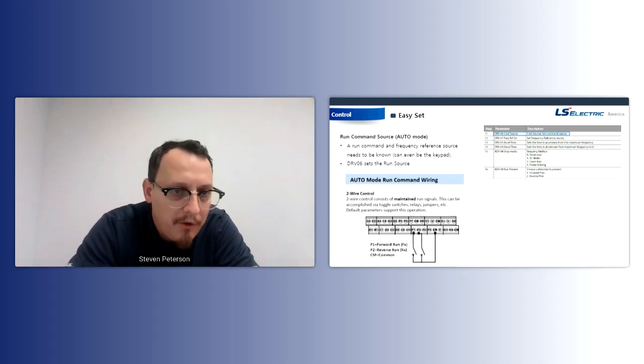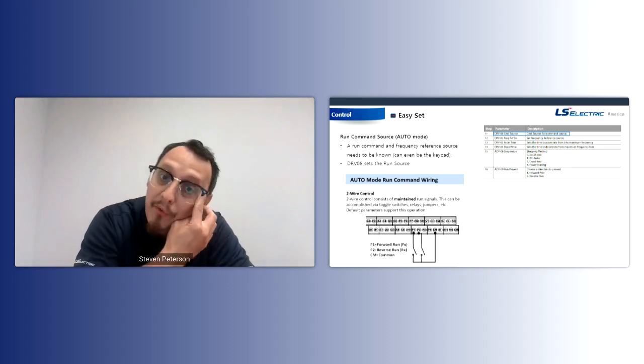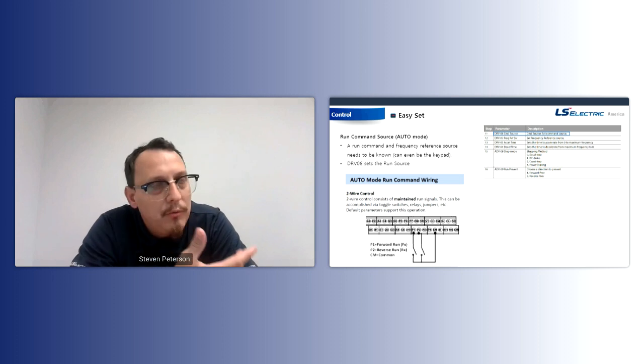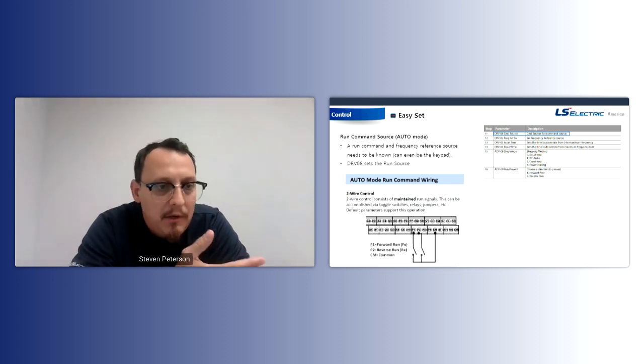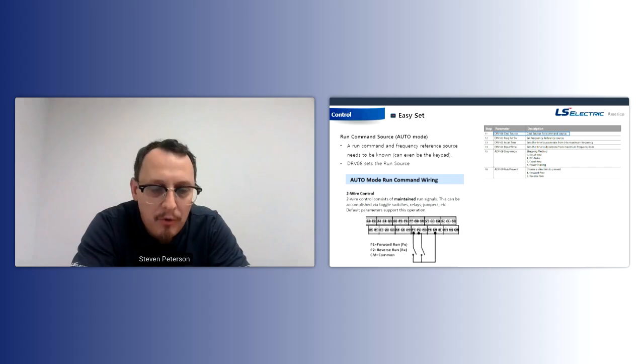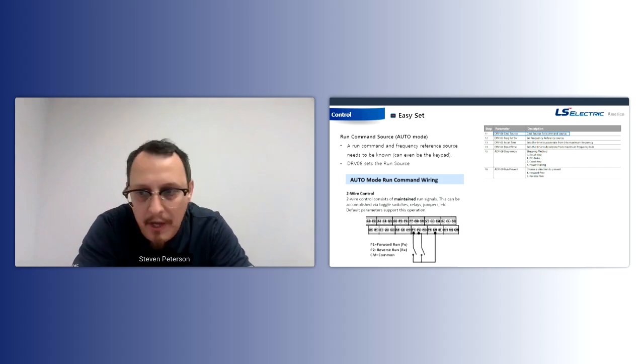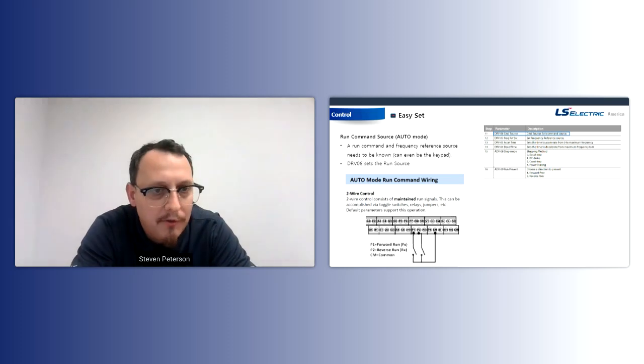your auto mode run command source, and then we're going to talk about frequency command source. So if we assume we're running a basic macro, so it's just general purpose, you start it, you stop it, you control the speed directly. Most of the time when you're running your VFD, you're going to be in auto. Okay, so auto mode is looking at two different parameters. It's looking at DRV 6 and 7. And again, you don't even need to remember the parameter names because you're just going down a linear list on the keypad when you first start up the drive.